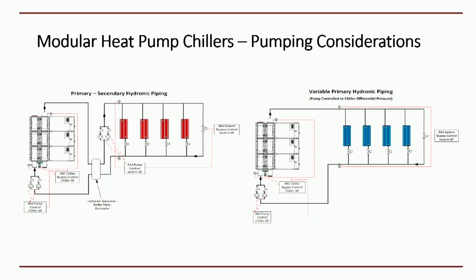And you can really get into a jam if you're not following some of these application guidelines from manufacturer to manufacturer. And the biggest thing is just remember, the connected load is not your building load, so these heat pumps do want to be satisfied. And when I talk about pumping considerations, it's just always making sure that that flow is there for both the building side and the heat pump side. And that is also a good segue into the next topic, which is on the controls.